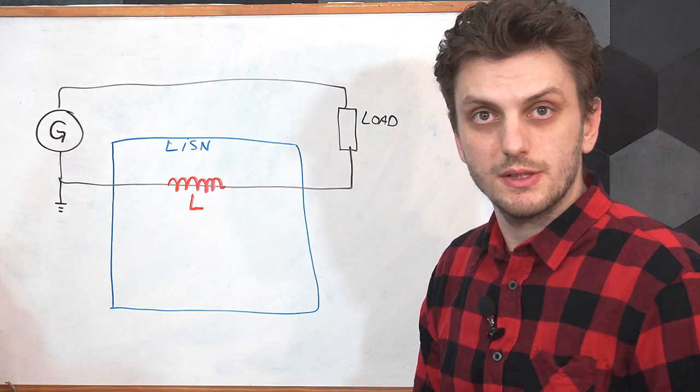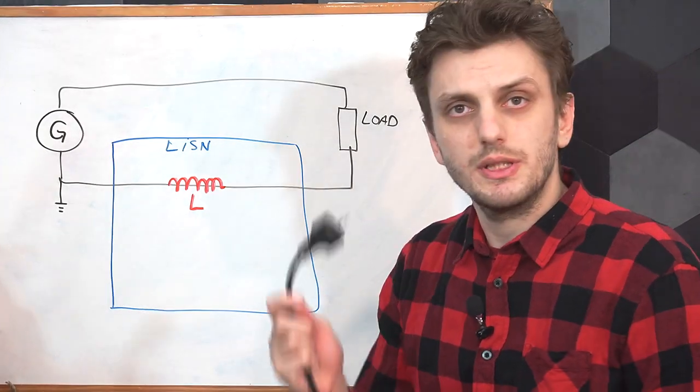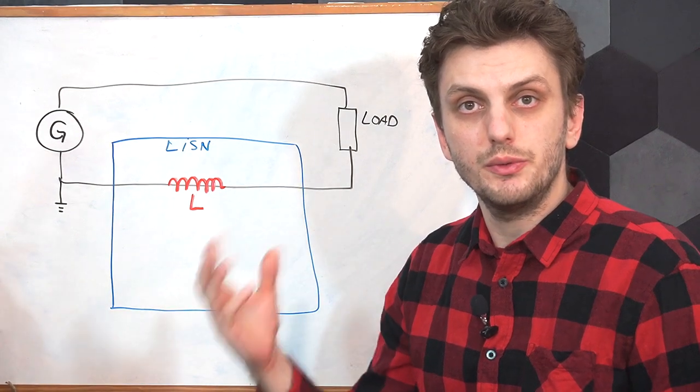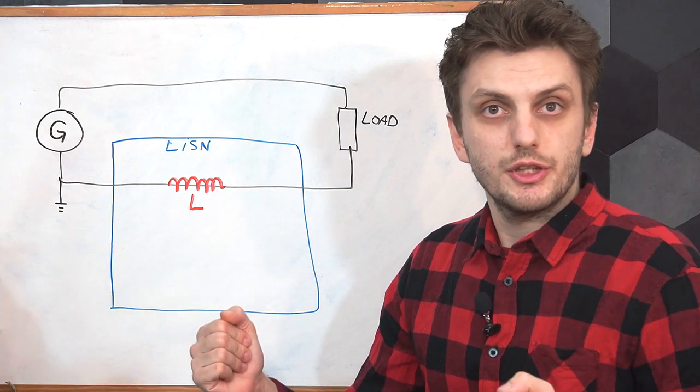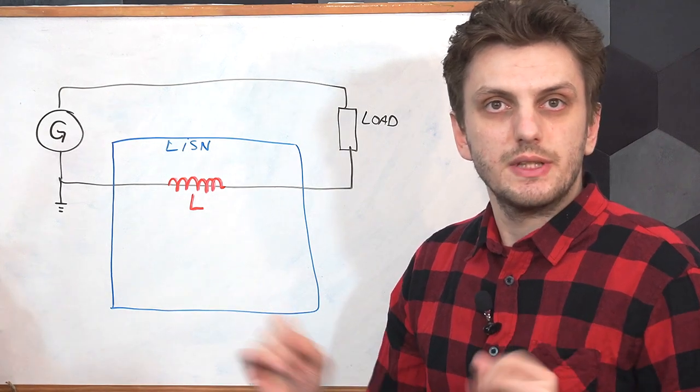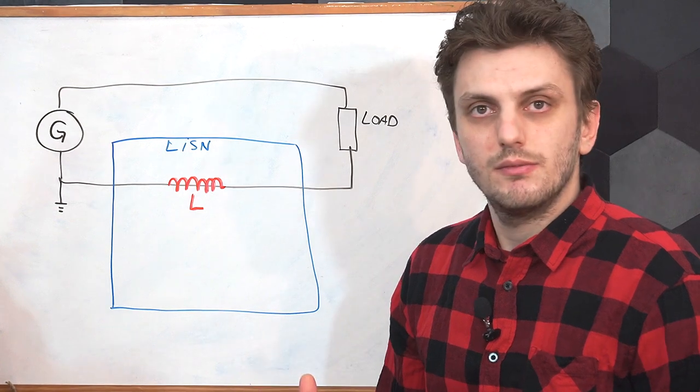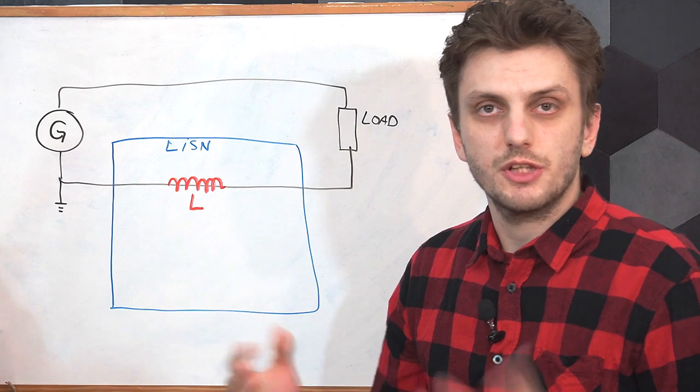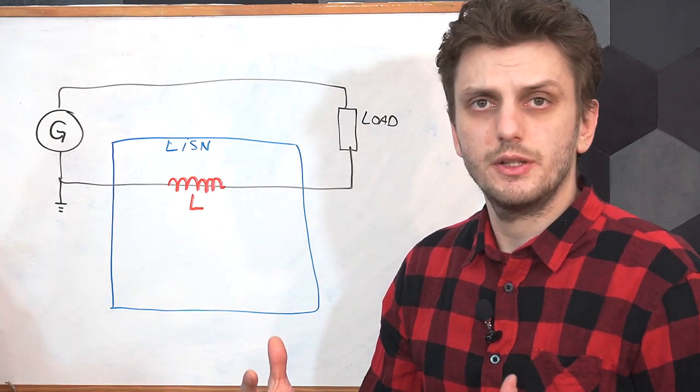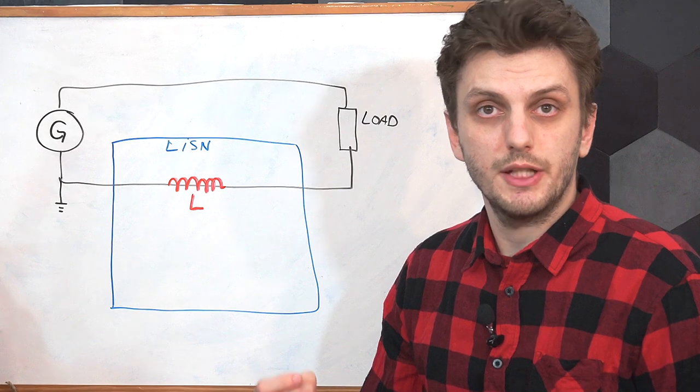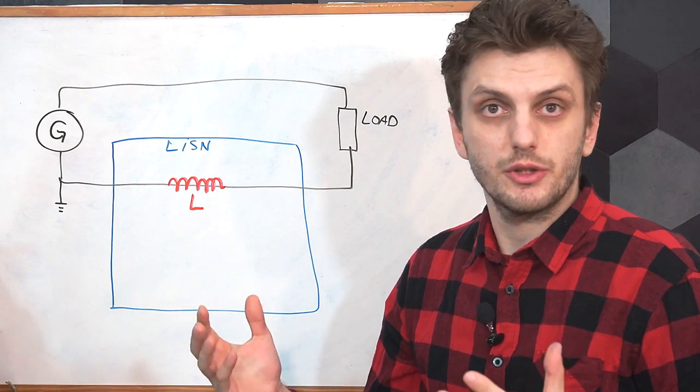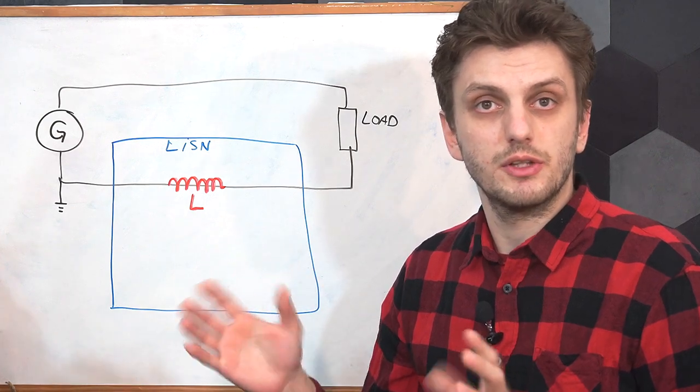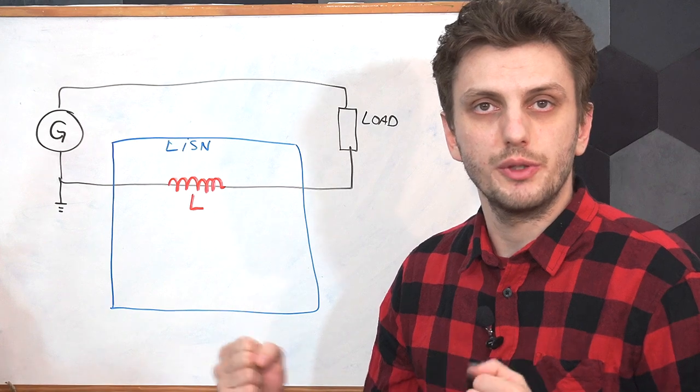Now, the value of this inductor has to do with the use case. So in things like AC power distribution, the length of cable between your unit and your local generator, so your local power transformer, is in the order of tens of meters. So in that case, a common inductor value is 50 microhenry, which is equivalent to about 25-30 meters of cable. On the other hand, in battery-powered applications, so like in automotive, cable lengths are much shorter, so you only have a few meters of cable, and there you will be using roughly 5 microhenrys, which is equivalent to about 3 meters.